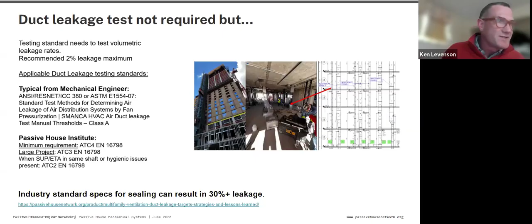And all of a sudden, we've seen projects in larger buildings where there's so much duct leakage that they can't get the ventilation numbers. They have to crank up the ventilation. So then they have much higher energy losses, and it throws the whole energy balance out of whack. And it can be a very serious problem. So making sure, like the building enclosure is airtight, we want the ventilation ductwork to be as carefully airtight practically. And we'll talk about a strategy to do that in a moment.